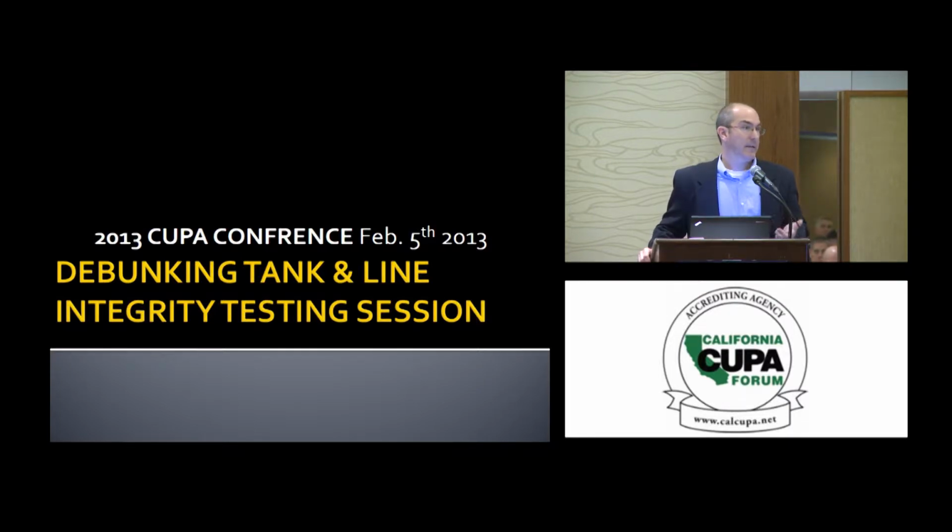A tank integrity test is kind of a real-time snapshot of the condition of the tank, as compared to some automatic tank gauge systems that may be running continuous leak detection, where they could have data that's been collected over a long period of time, maybe a month or so. So it may not be indicative if a leak had just started to occur that day. And then a tank integrity test done in the underfill mode is usually followed up by an ullage test that would check for any leaks that are occurring in the non-wetted portion of the tank.